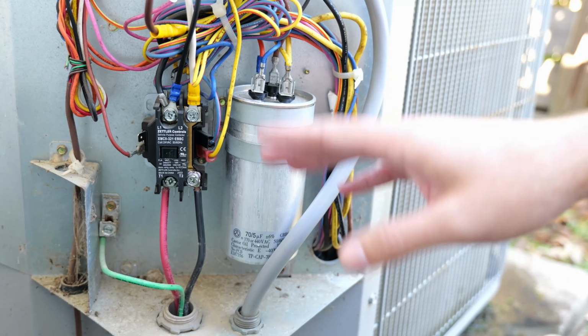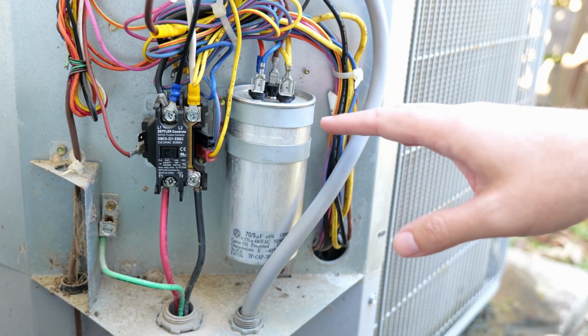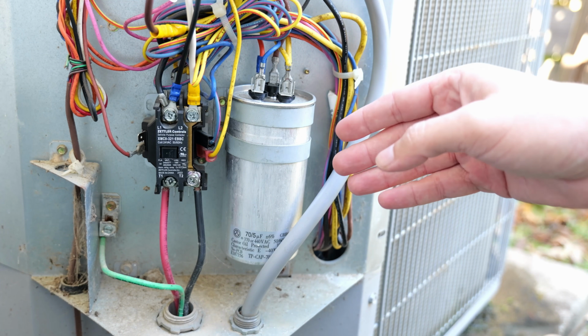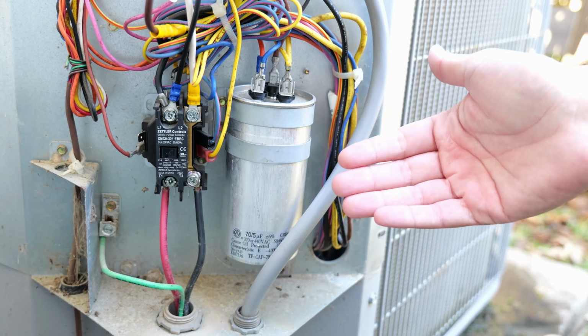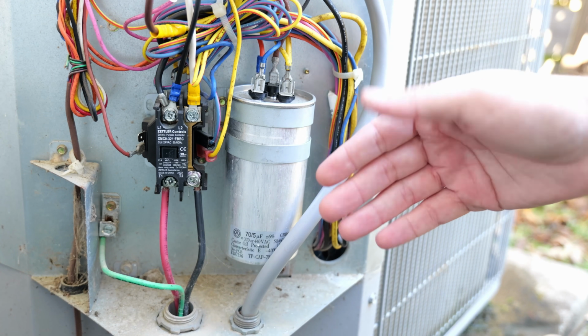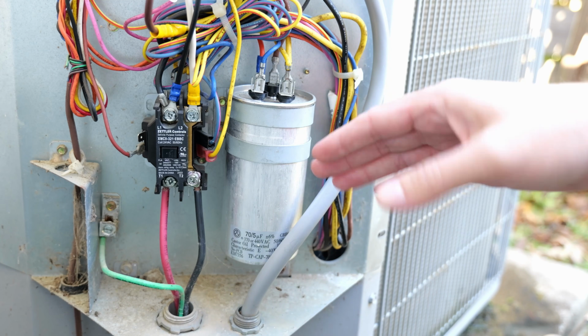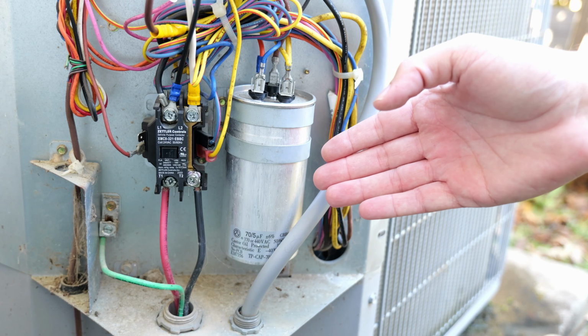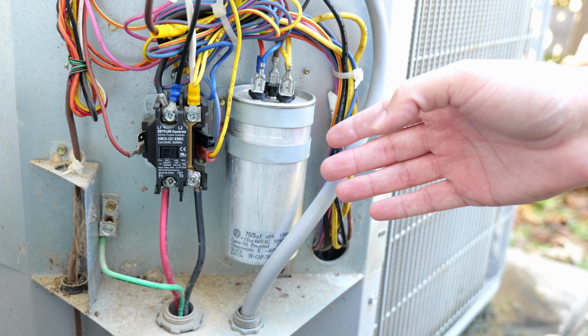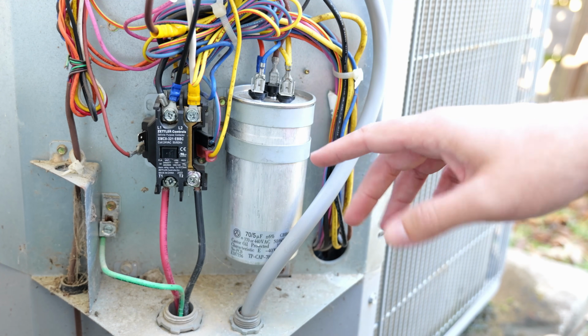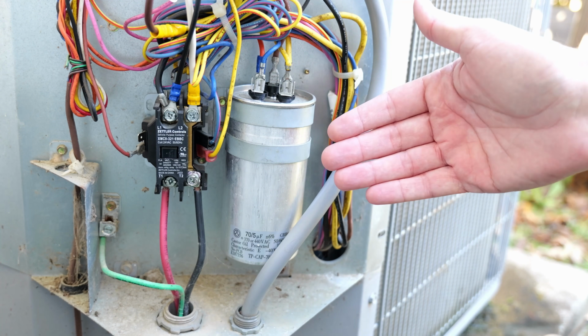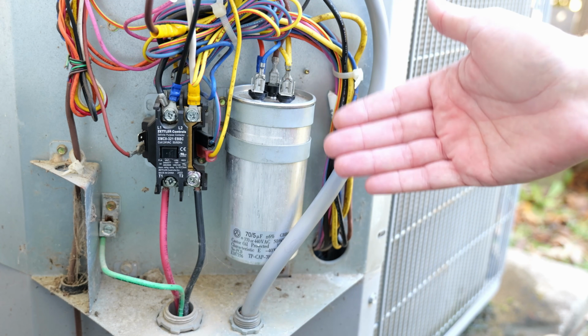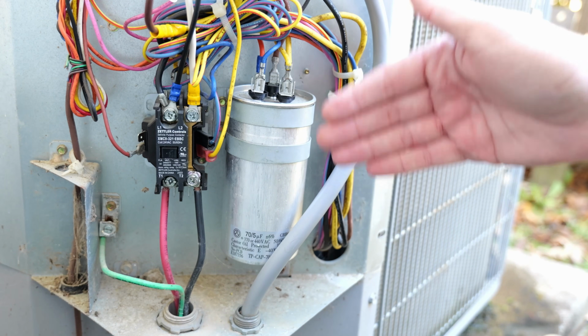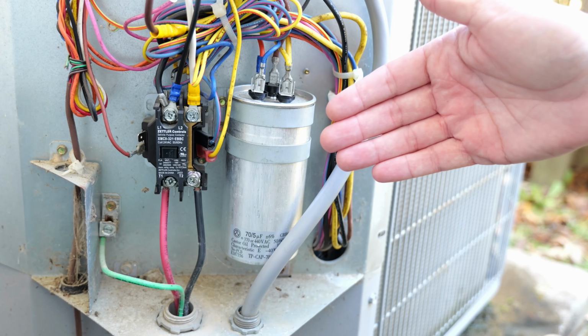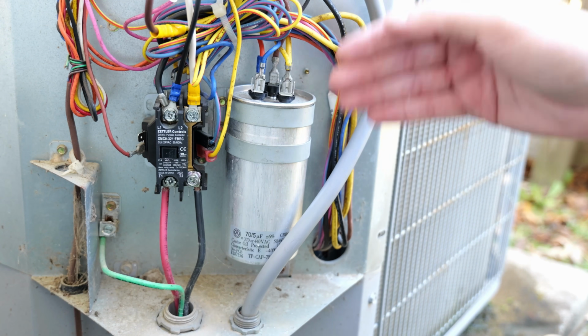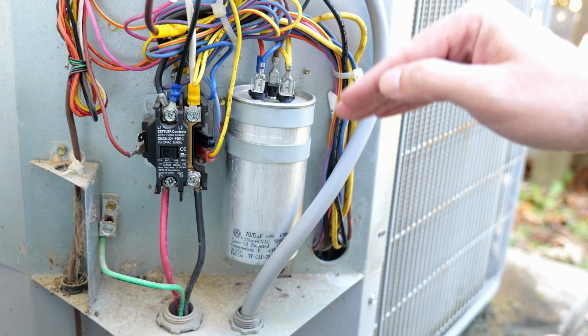Now that we've verified the power is in fact off, before I start working on this capacitor and start touching things - these capacitors can possibly still hold a charge, and one that can pack a pretty good punch. Again, these basically are storing energy. However, once the unit is off and disconnected, this capacitor should have already discharged naturally through the windings, but sometimes they do still hold a little bit of a charge. So before anybody starts working on this, the best thing to do is always make sure these are actually discharged first.